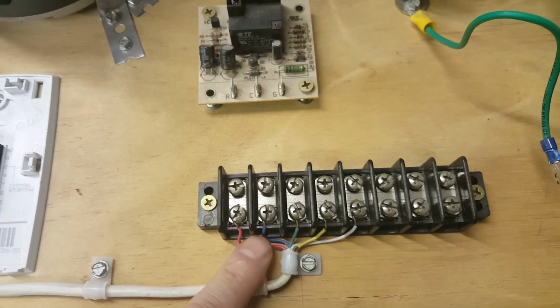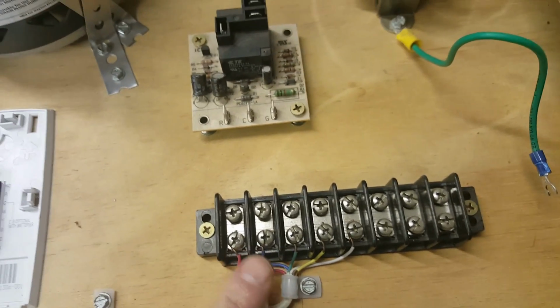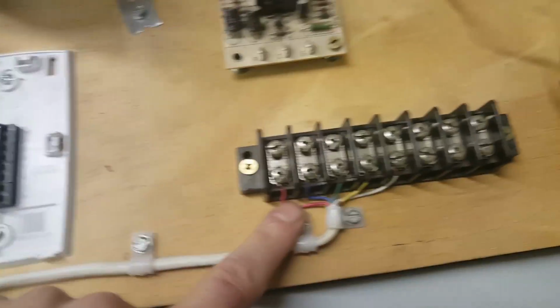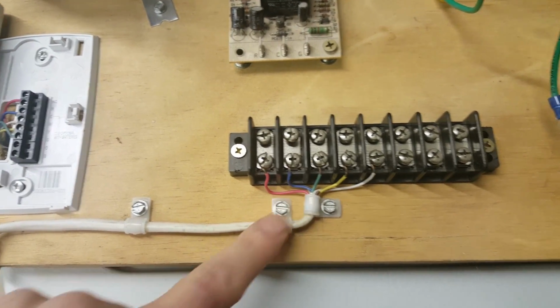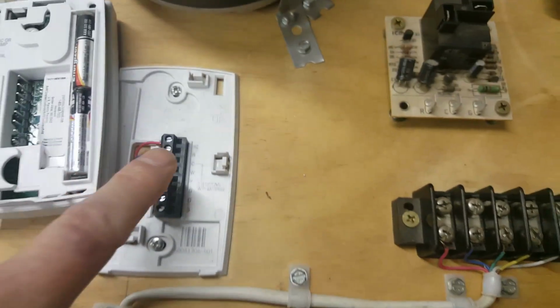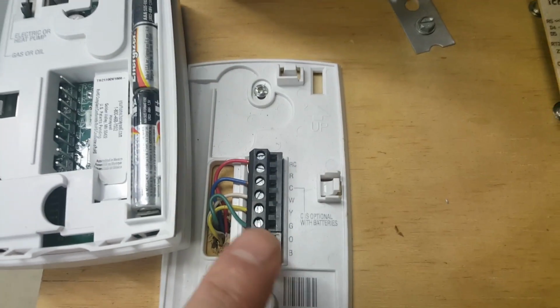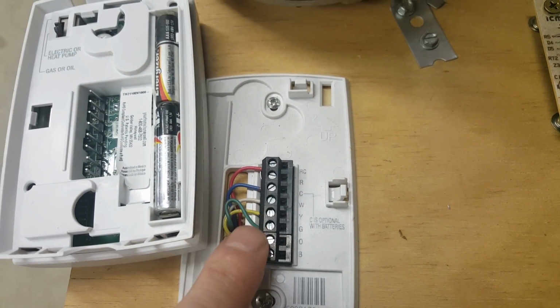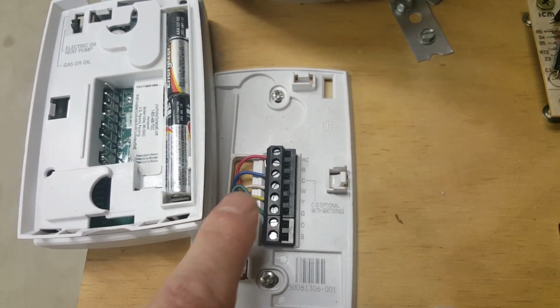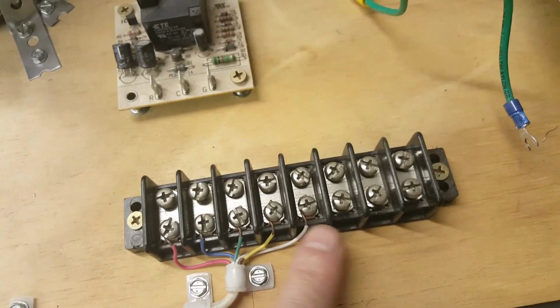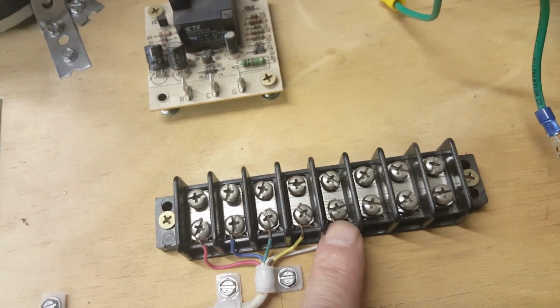I like to look at this as 2 wires, even though we have 5 going out to the thermostat. I like to look at it from a troubleshooting standpoint of 2 wires, the 24 volt wires going out to the stat, and the actual 3 wires coming back, which is your W for your heating. If you're in the heating mode, R is taking a ride on W back out here to call for heat to finish the circuit.